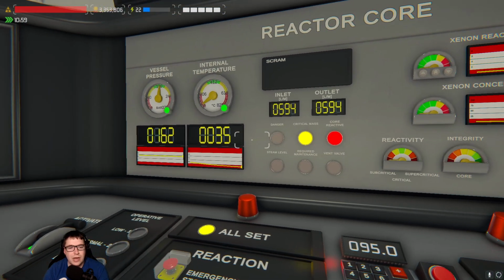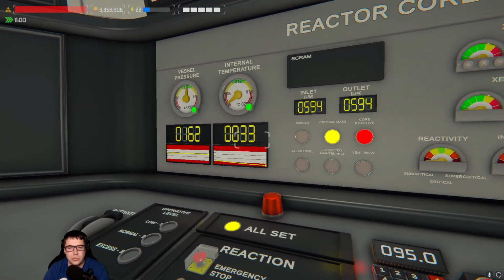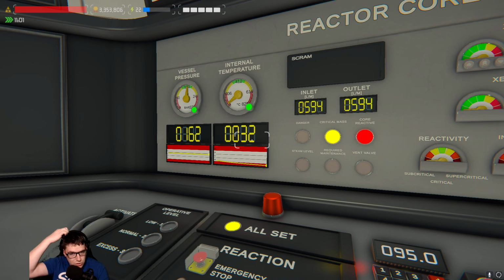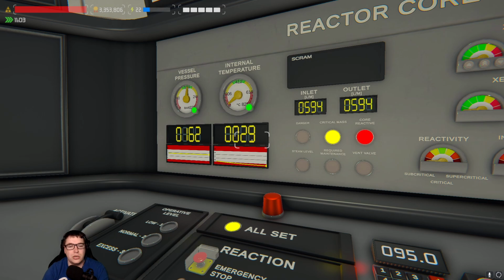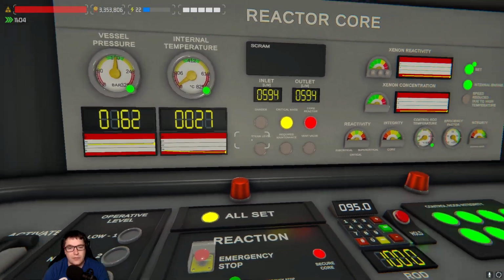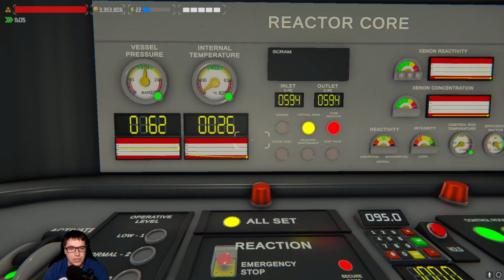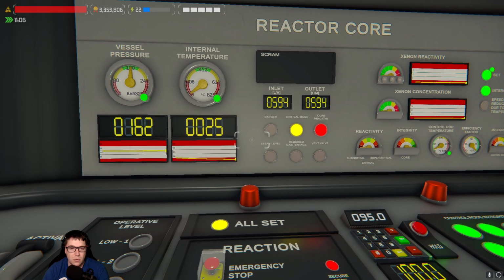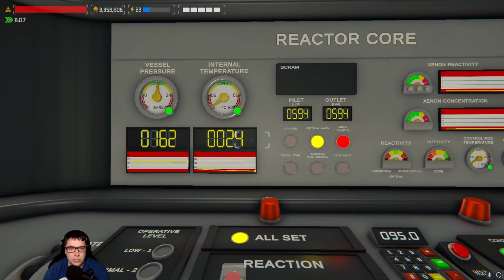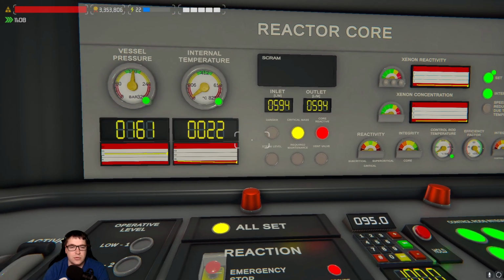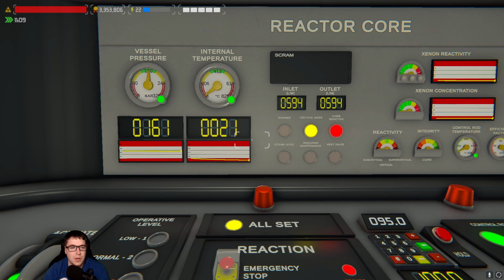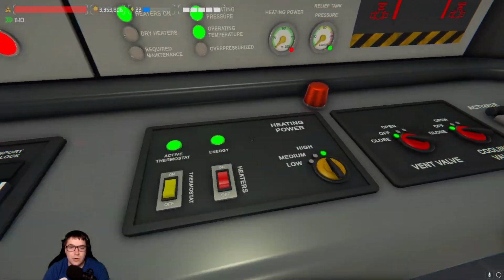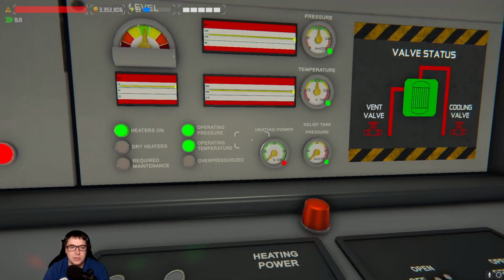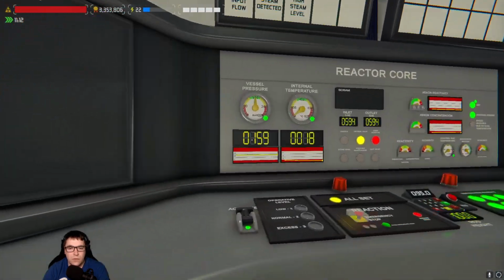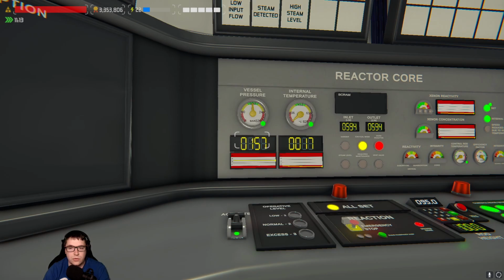What we do need to do now is just run the pumps for a bit, because inevitably, once we stop the water pumps, the core is still hot in itself, so the internal temperature will start to climb, and due to reaching that 55-degree mark, will activate the reactivity once more. So I'd suggest keeping the pumps running for an hour or so. But what we can do now is switch off our heating elements, which will cause the pressure within the vessel to also drop.